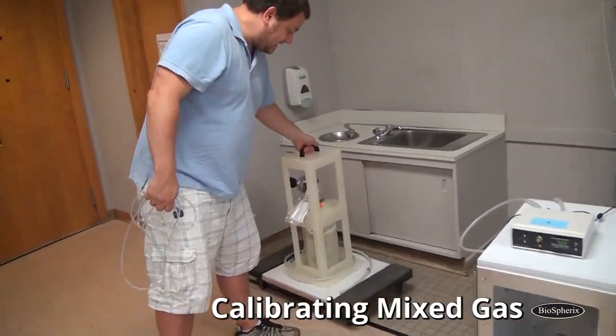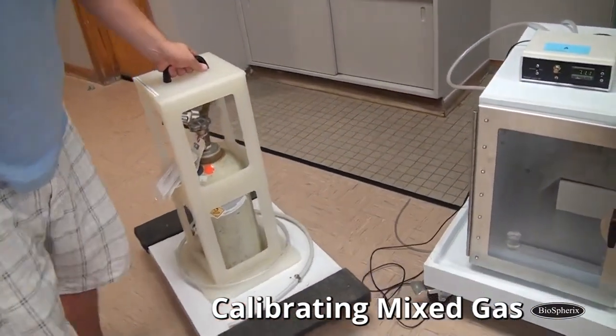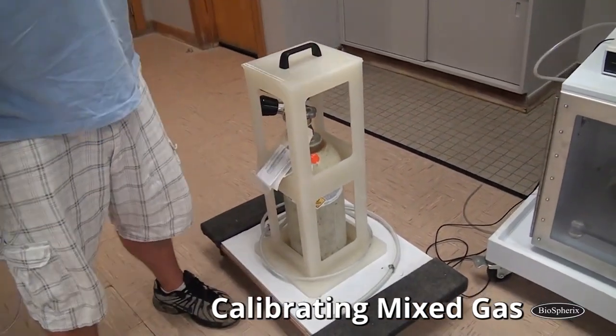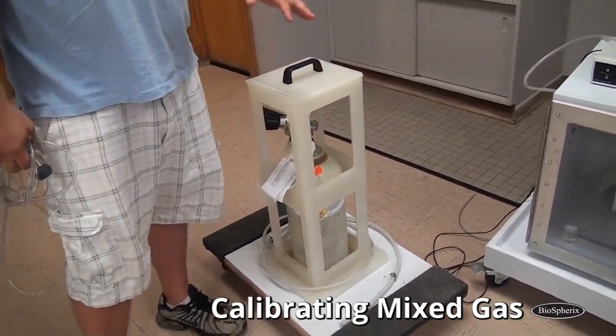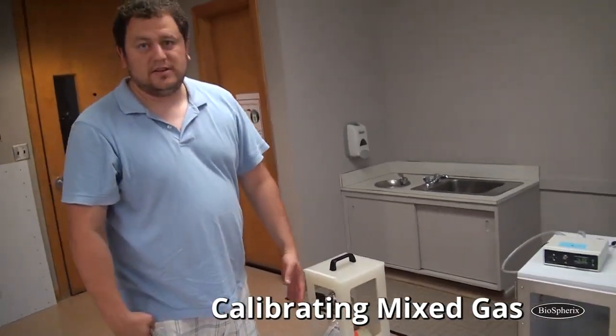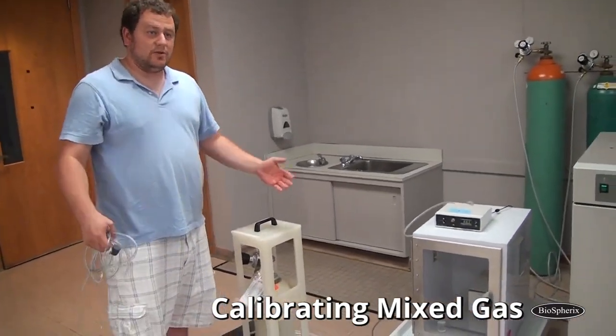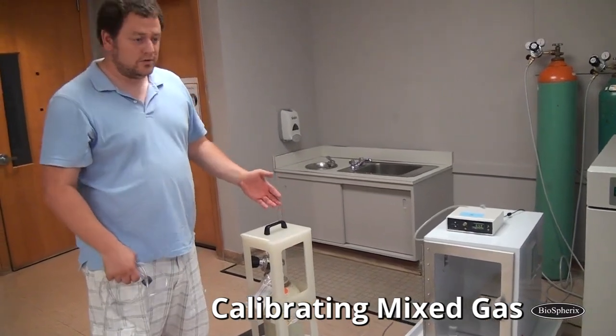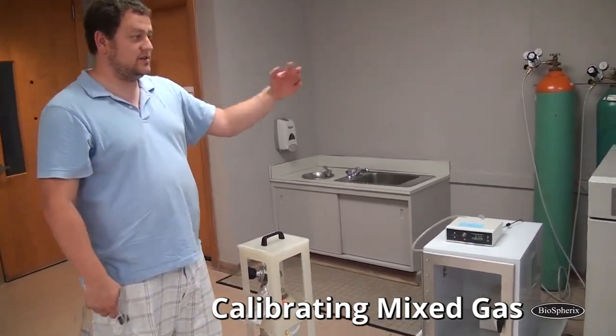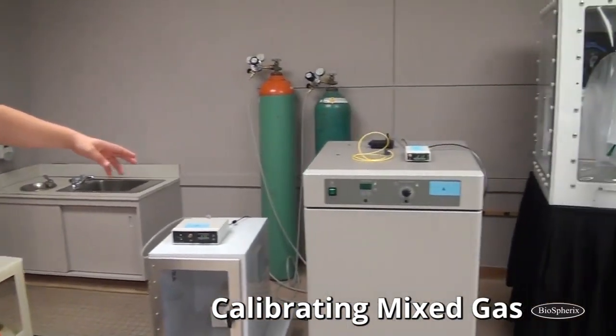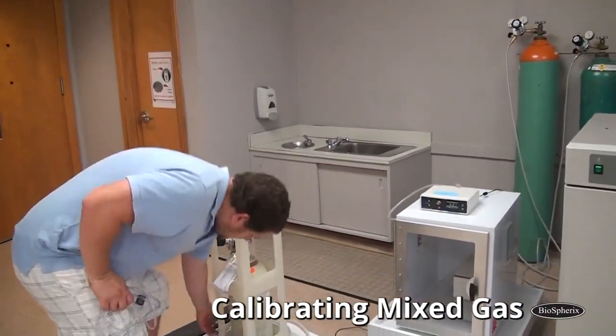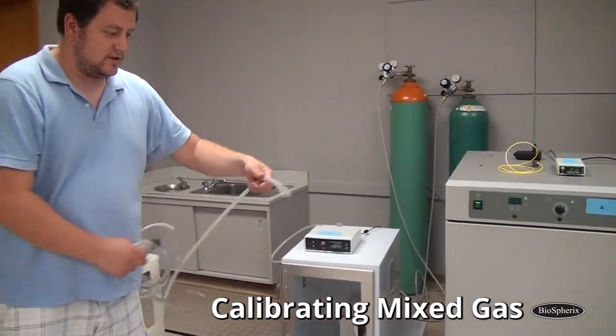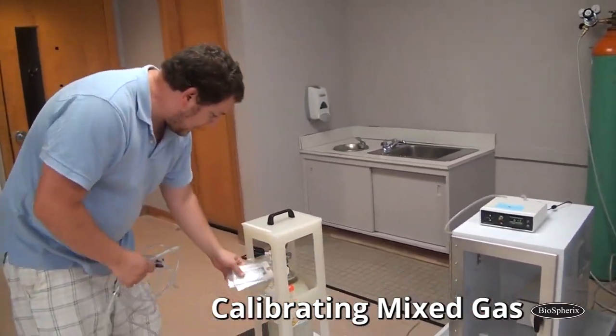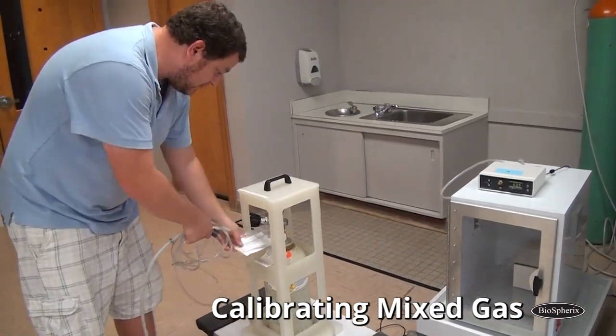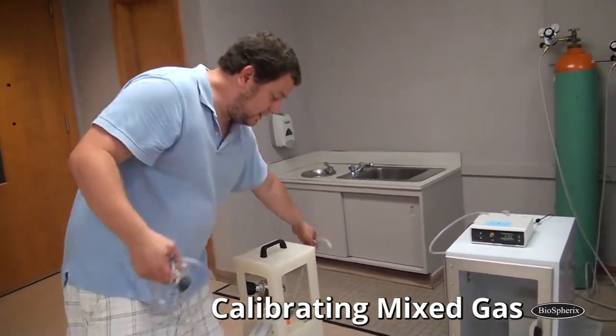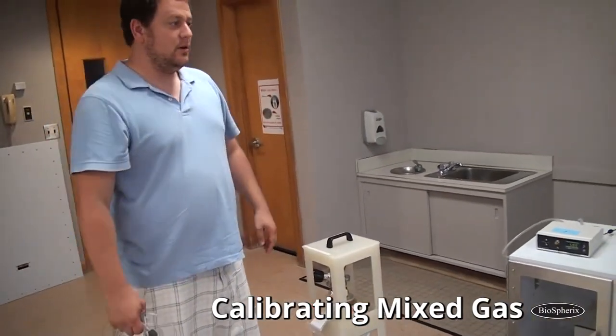So I brought up our mixed gas tank here. And what this is, it's 90% oxygen and a balance of CO2. So what we're doing is 2 gas known certified levels. So you do your zero just like we did for the P110, and then you would hook up your mix tank to the controller, and it would be whatever the tag says. In this case, it's exactly 90.0 for oxygen, and you would calibrate your span to 90.0.